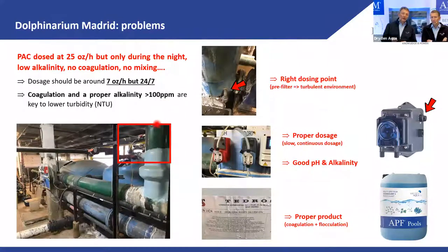The green line shows the pipe from the pump to the filters. They had the flocculant injection point after the pump — in a 400 mm (roughly 16-inch) pipe — so the flocculant wasn't mixed; it just traveled along the tube with no reaction. We changed this in 10 minutes, moving the injection point to the strainer just before the pump.